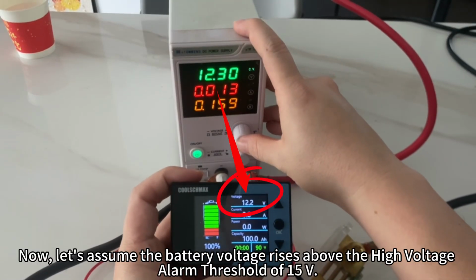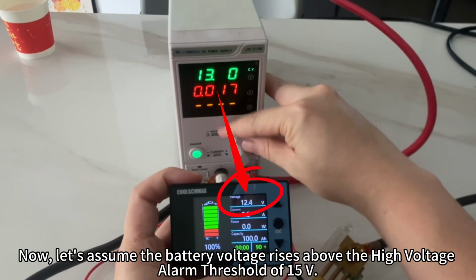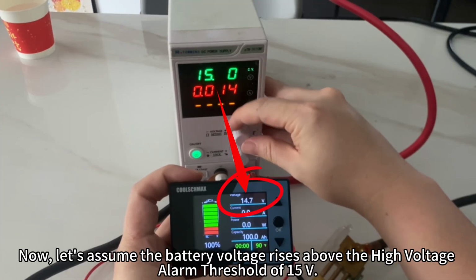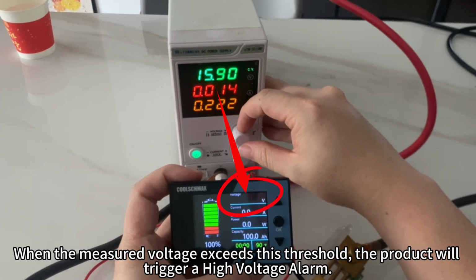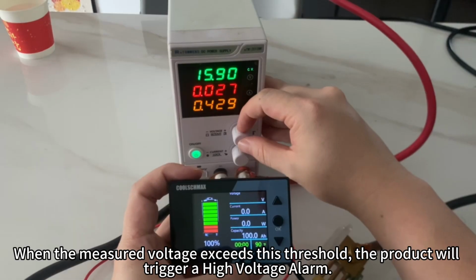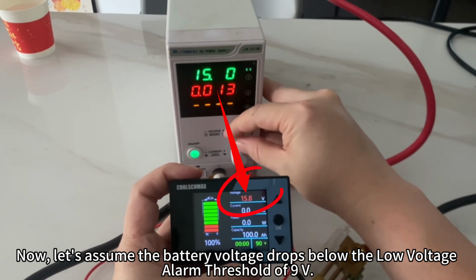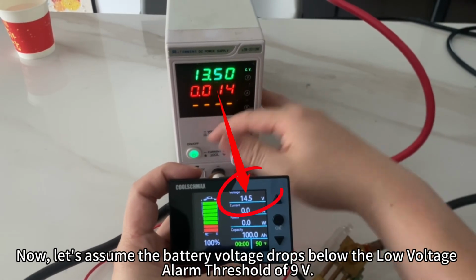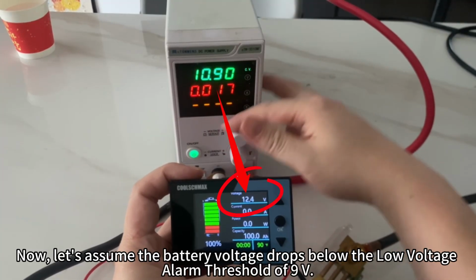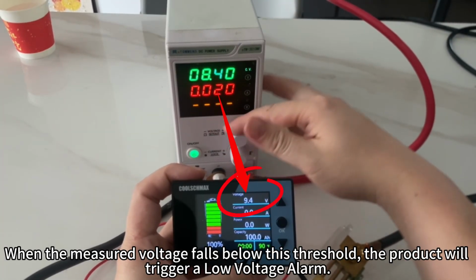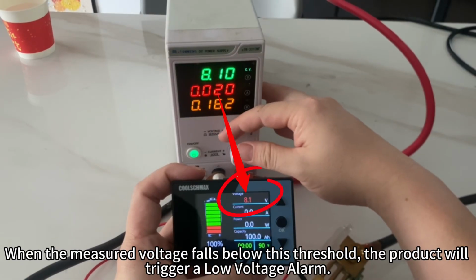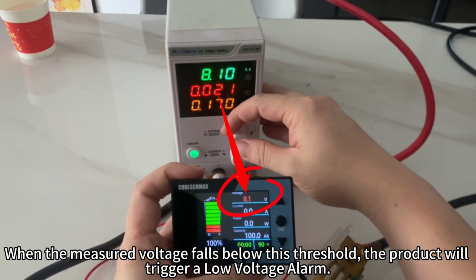Now, let's assume the battery voltage rises above the high voltage alarm threshold of 15V. When the measured voltage exceeds this threshold, the product will trigger a high voltage alarm. Now, let's assume the battery voltage drops below the low voltage alarm threshold of 9V. When the measured voltage falls below this threshold, the product will trigger a low voltage alarm.